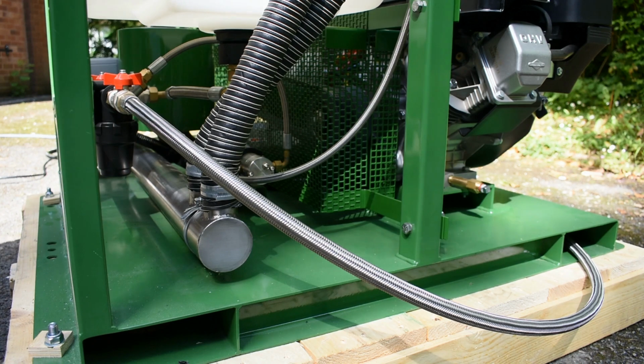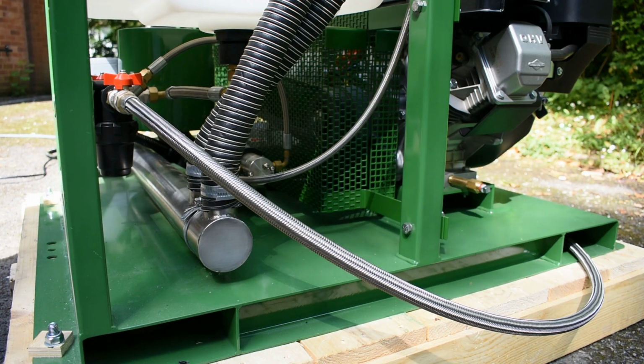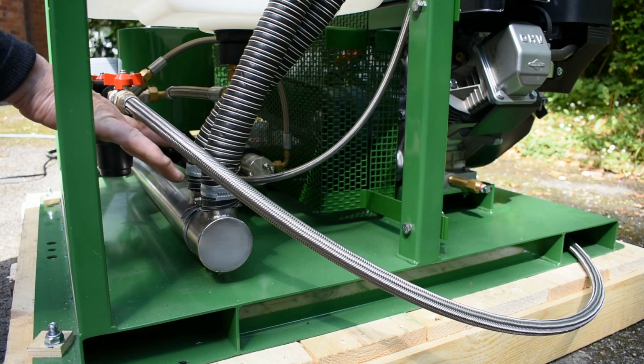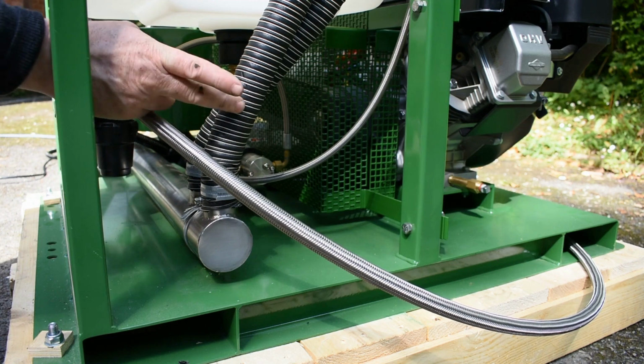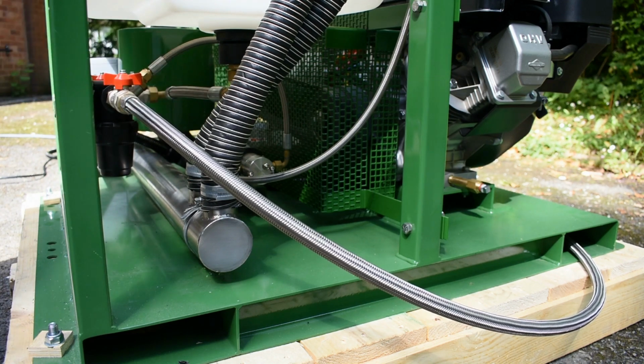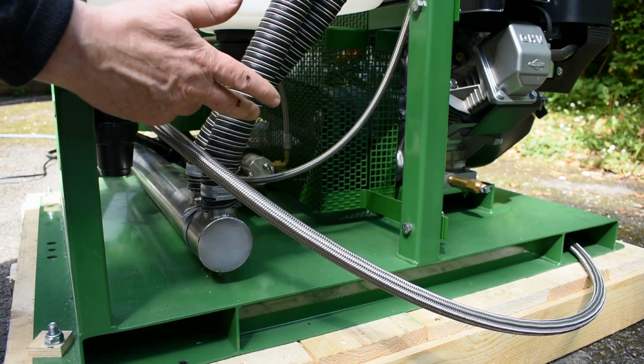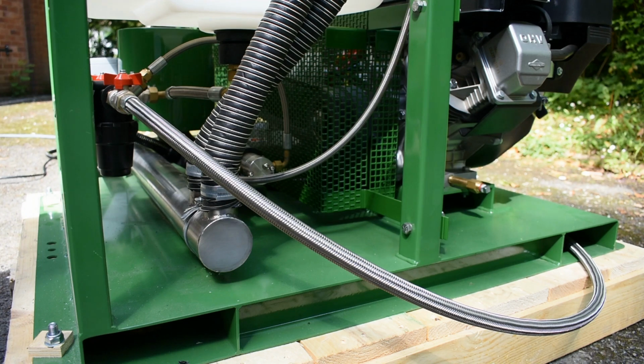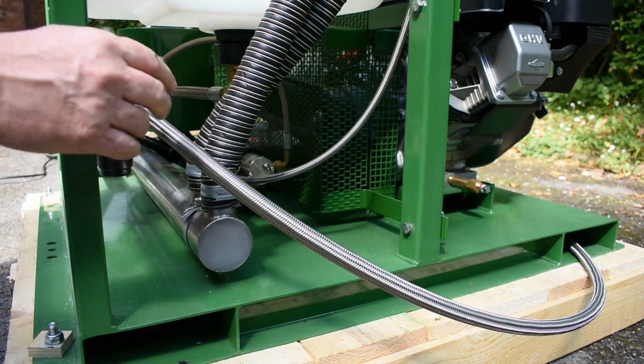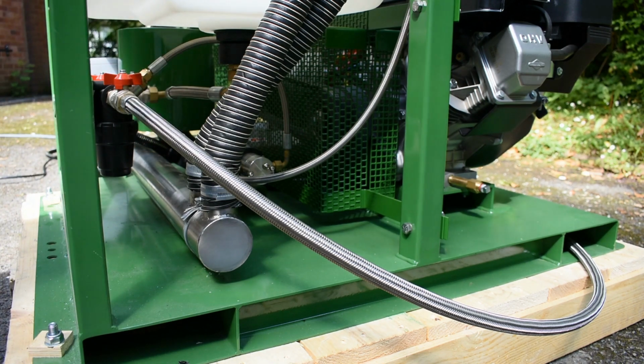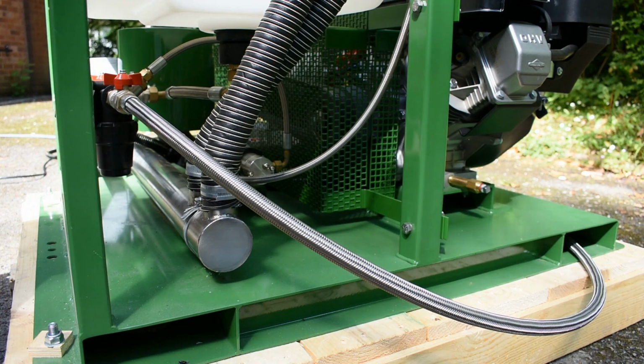Okay, so just to complete the air circuit, you can see there's the outlet pipe. Again, this is a stainless steel manifold, and you've got 2 outlets to the pipe. These are temperature resistant hose tubing, which goes up to the atomizer. So these are under pressure, and again, the pressure is very important for creating the correct droplet size. So that pressure in these hoses we monitor with the air sensor, just to check that it's the correct pressure. Otherwise it'll cut off if the pressure is insufficient.